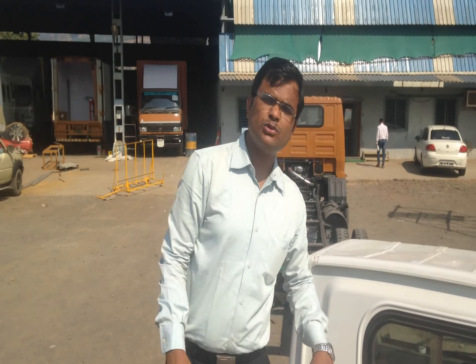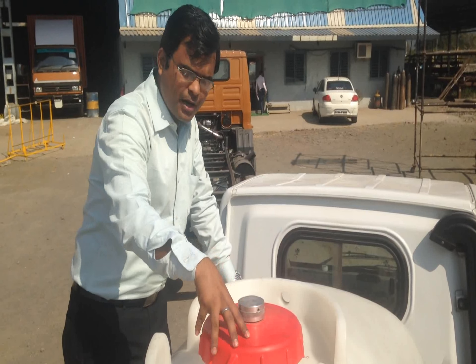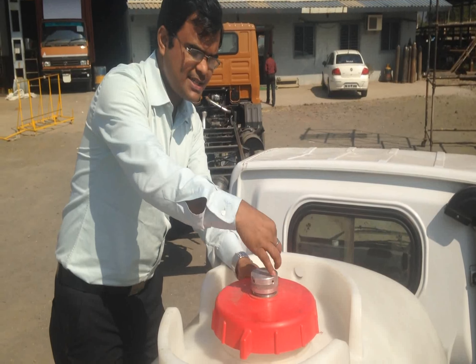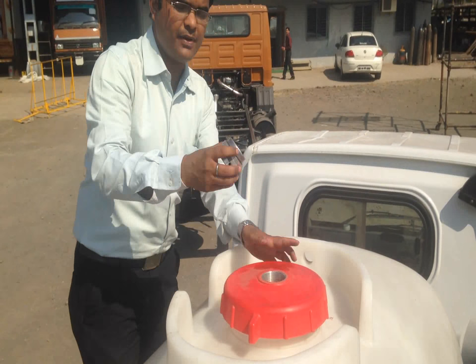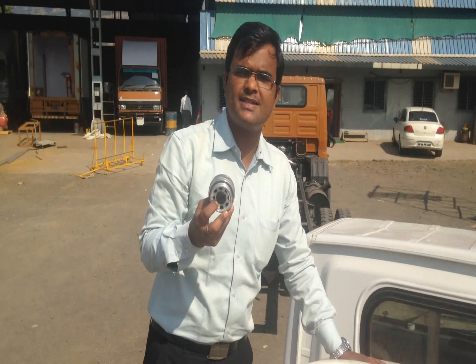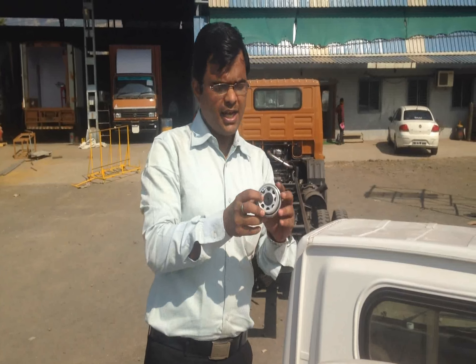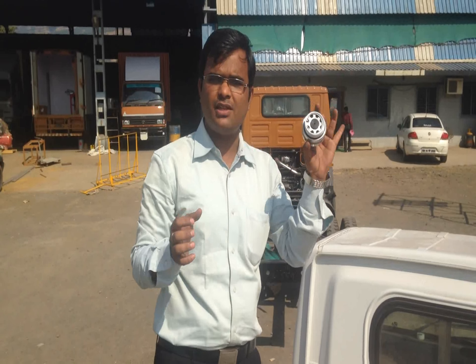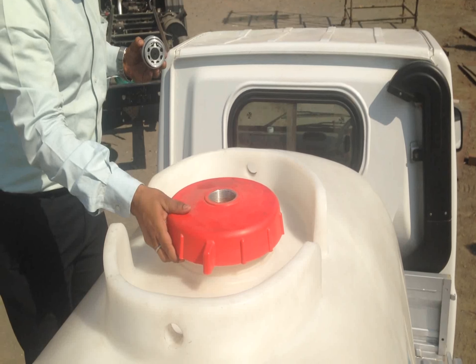Let me explain the process of filling the tank. As you can see on the top of the tank, there are two openings: a big cap and a smaller opening. While loading the vehicle, you can see there is a spring-loaded air vent, which is an additional safety feature. In case any pressure is generated inside the tank due to fuel movement on the construction site, it is released to the atmosphere through the air vent, which also acts as your fueling point. The second, bigger opening allows you to remove the cap and clean the tank if required.